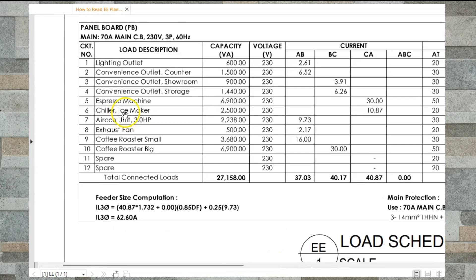So kung nakita mo to, meron siyang 11 circuits. Ibig sabihin niyan, meron tayong 12 circuit breaker or dalawang branches. So itong ating circuit number 1, which is for lighting outlet. So ito yung sa ilaw na meron siyang 600 VA. Yung pangalawa is convenience outlet na nasa counter, 1,500 VA. And then convenience outlet na sa showroom, ito yung meron siyang rating na 900 VA.